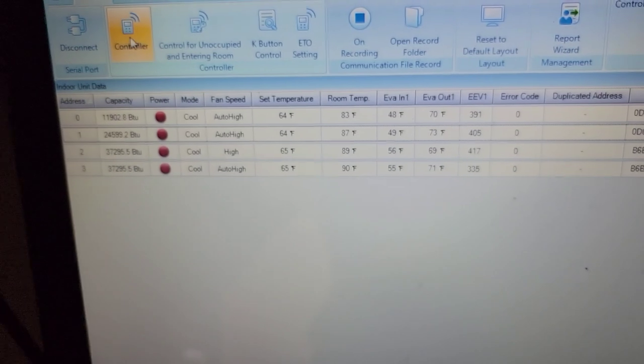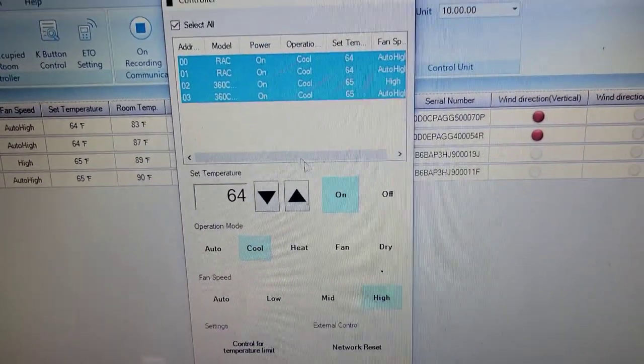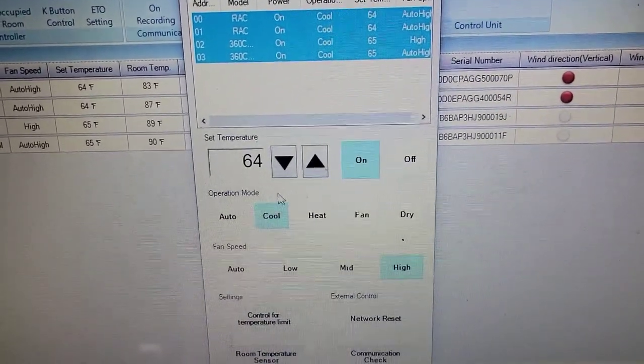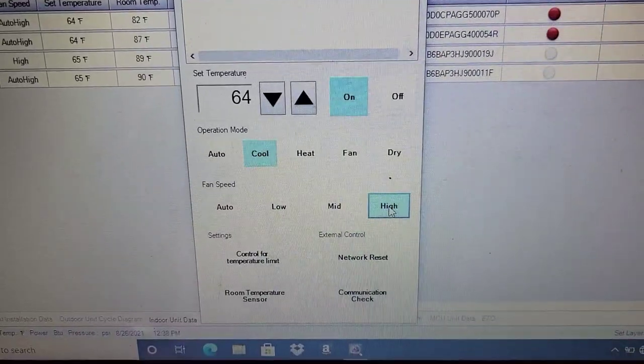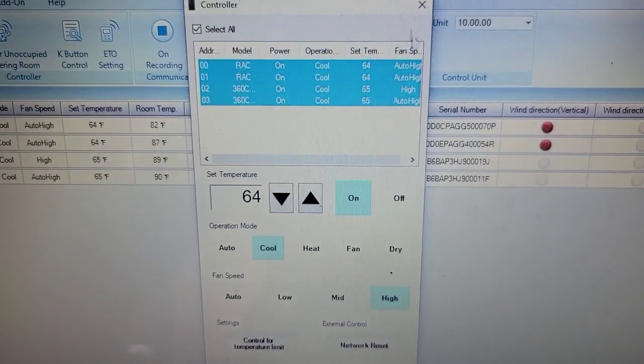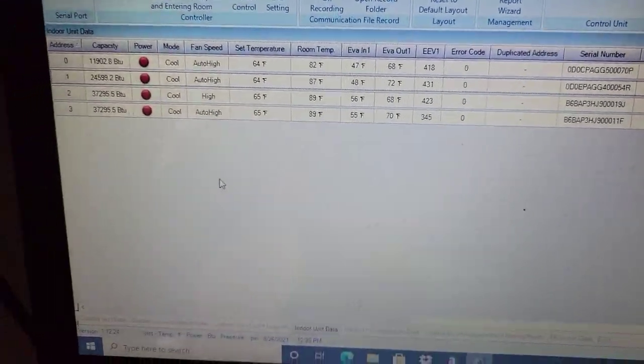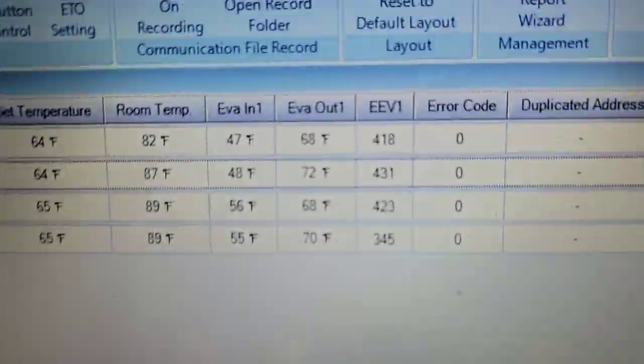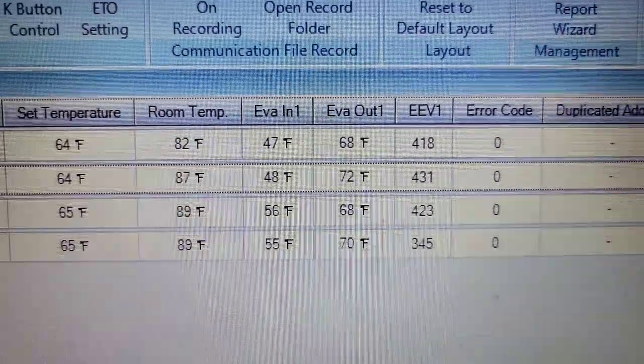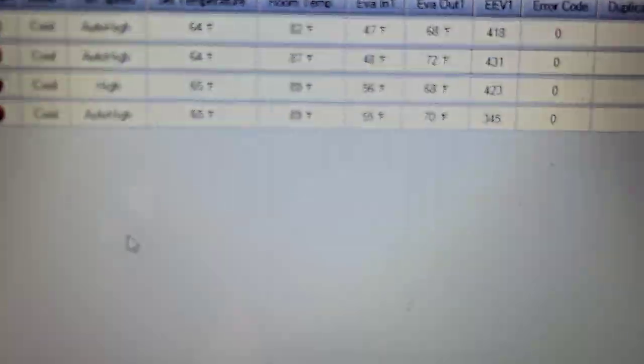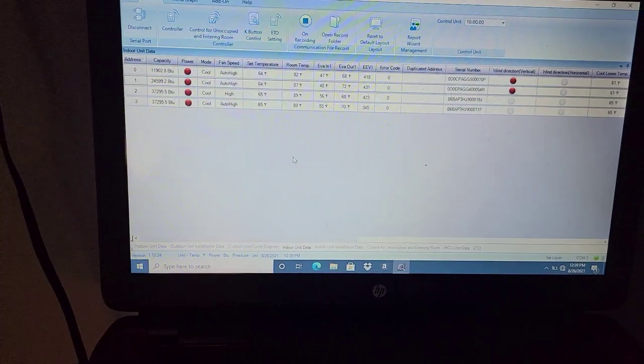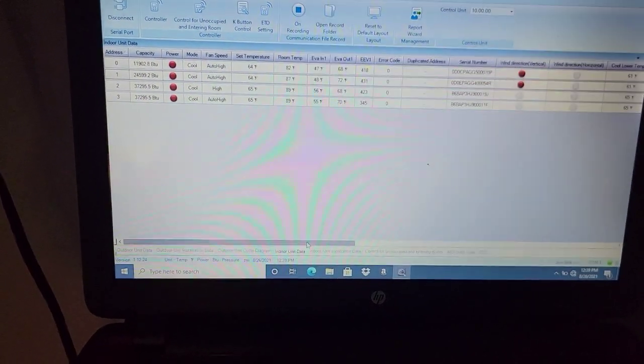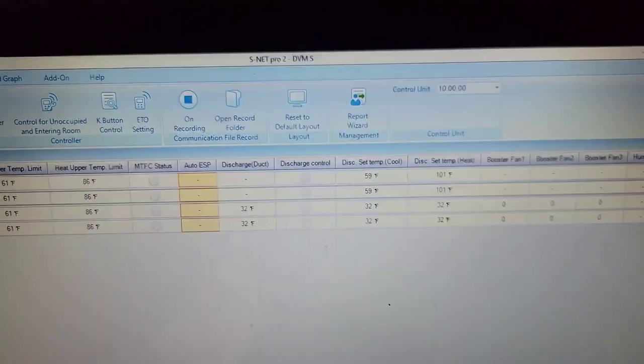See the controllers right here. You can push select all, then put the system to on, temperature set to 64, operation mode cool, and then fan speed on high for all those units because I want to see this outdoor unit ramp up. Look at the EEV positions. Evaporator inlet, evaporator outlet, 48 degrees, 72 degrees. Room temperature is 89 degrees. I love S net because I don't have to go individually turn all of the units on via the wired controllers or wireless controllers.